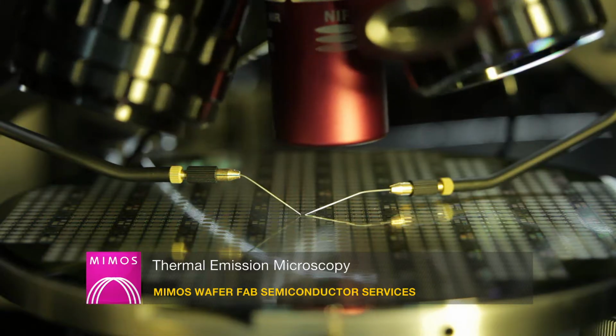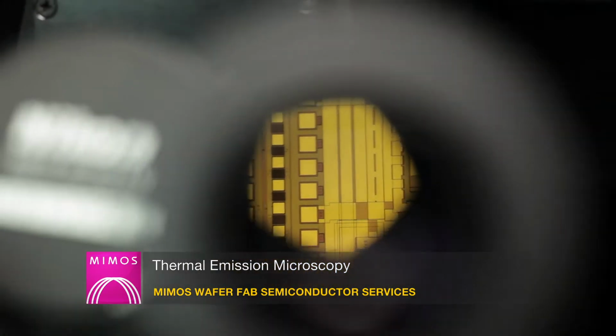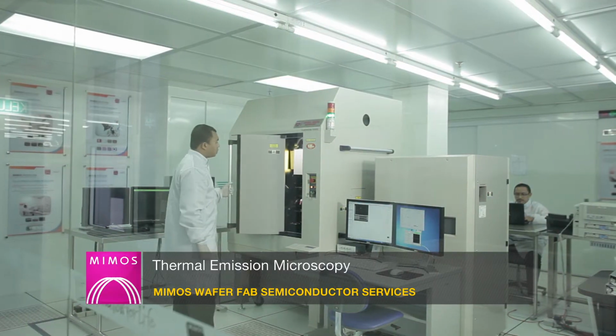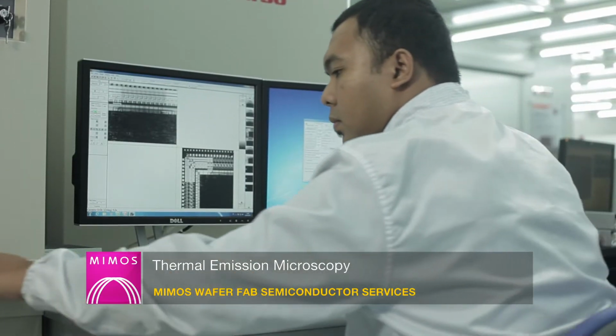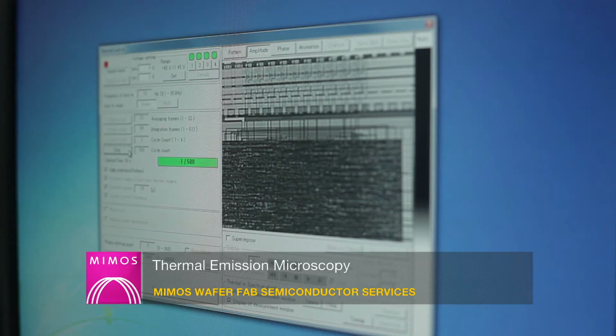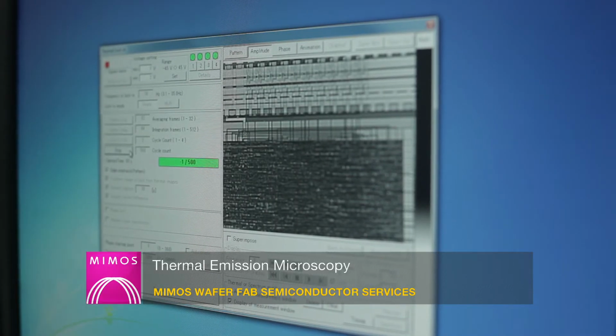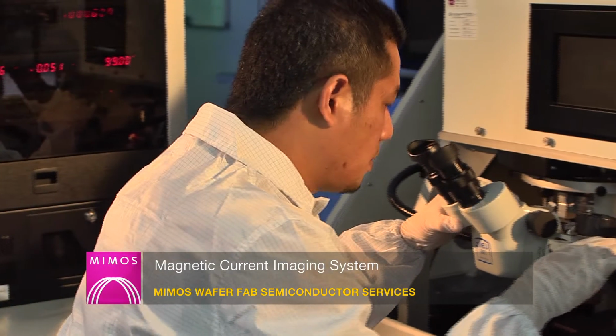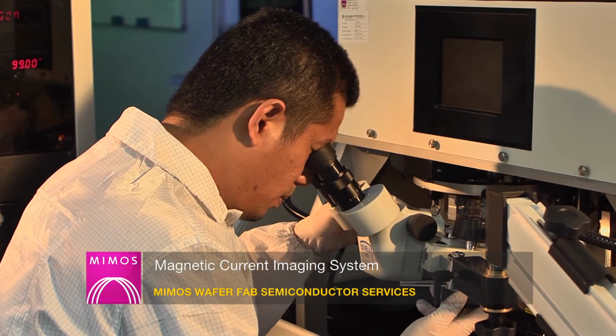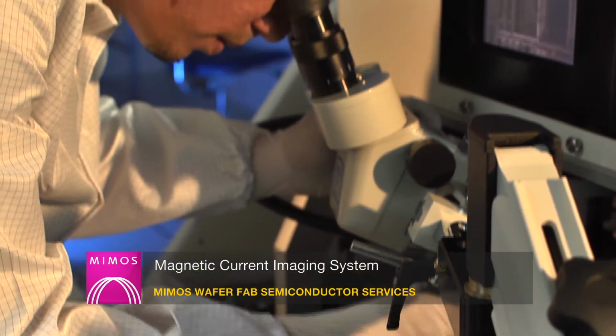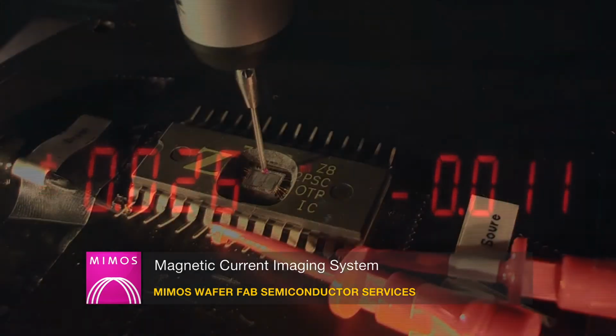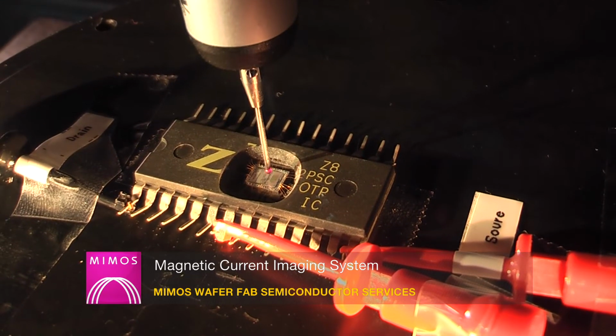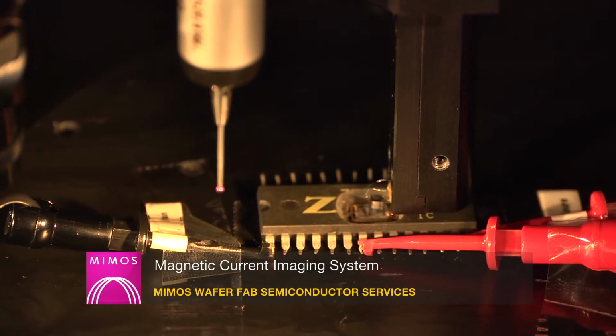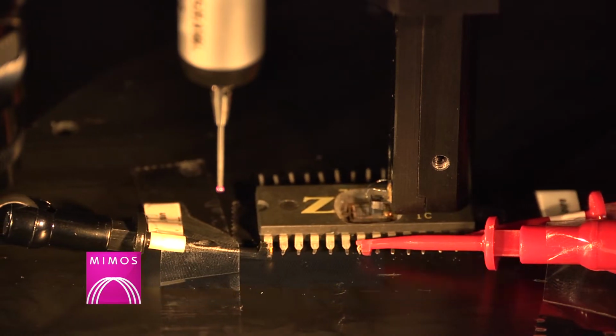Thermal emission microscope is a failure location tool equipped with a high sensitivity indium antimonide camera that detects internal heat emissions from semiconductor devices. Magnetic current imaging system is used to localize semiconductor failures through the measurement of weak magnetic fields. By mapping out the current flow in an IC or package, all types of shorts and conductive paths can be localized.